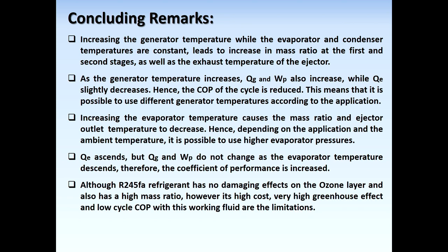In summary, increasing the generator temperature while evaporator and condenser temperatures are constant reduces the COP of the cycle. This means it is possible to use different generator temperatures according to the application. Increasing the evaporator temperature causes the mass ratio and ejector outlet temperature to decrease; depending on the application and ambient temperature, it is possible to use higher evaporator pressures.